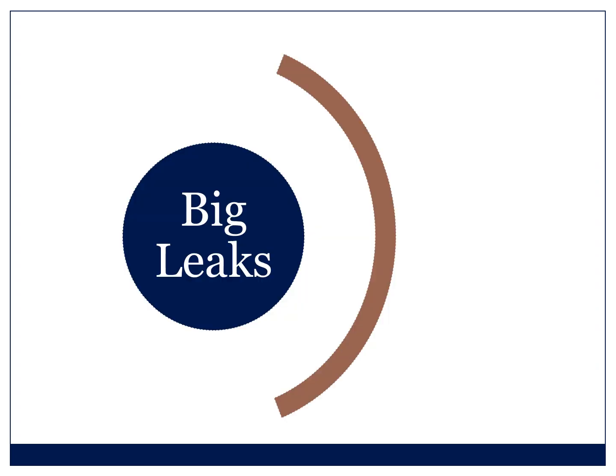Now, with big leaks, it's worth remembering that there are actually 3 main causes. By big leak, I mean you can't even get pressure in the bag. You've got your flows high, and you press the bag and the air just goes. Those big leaks are worth knowing. Where do I look first?